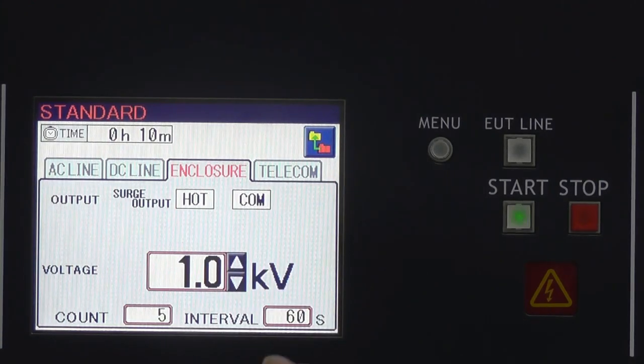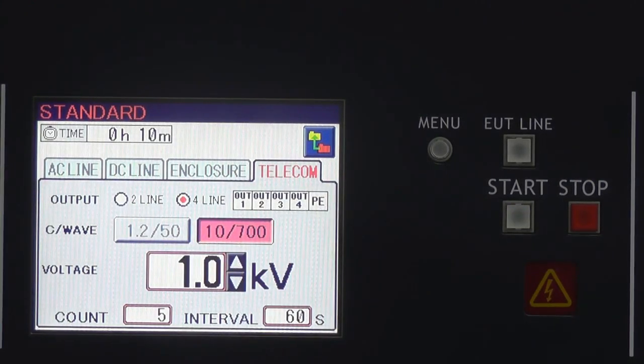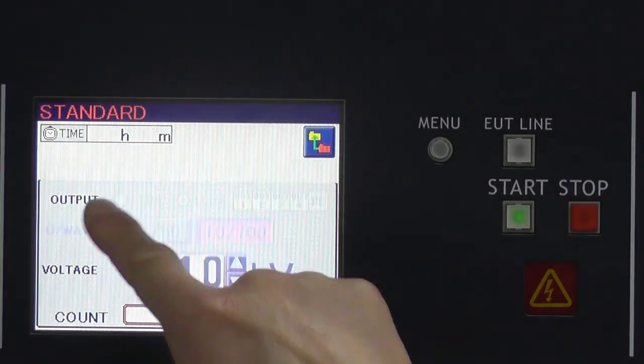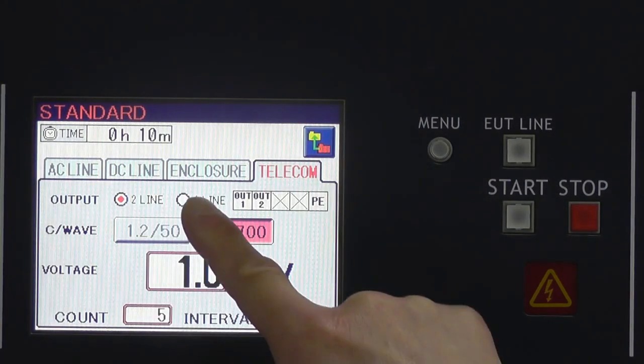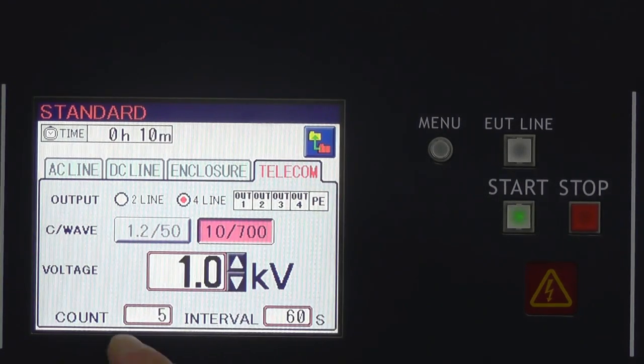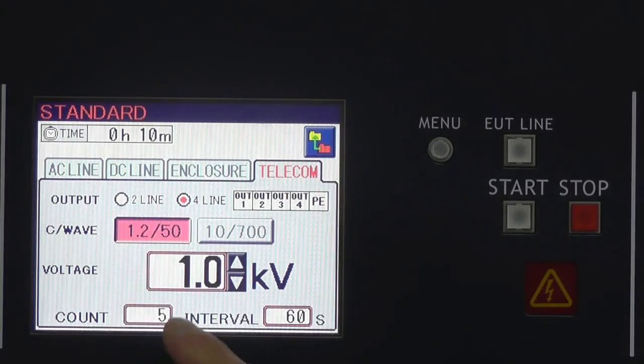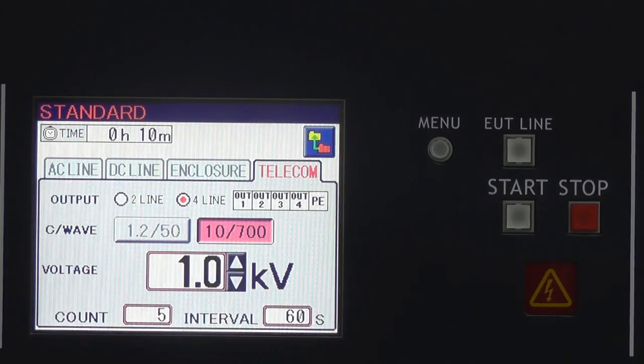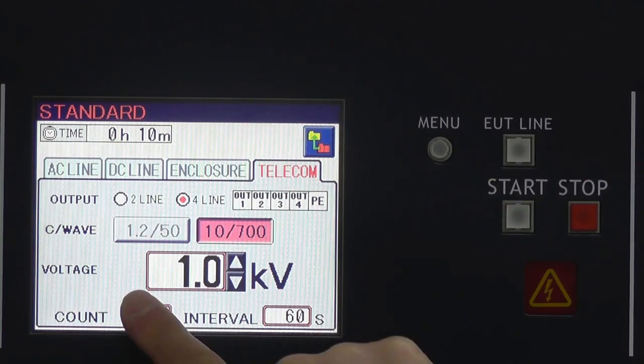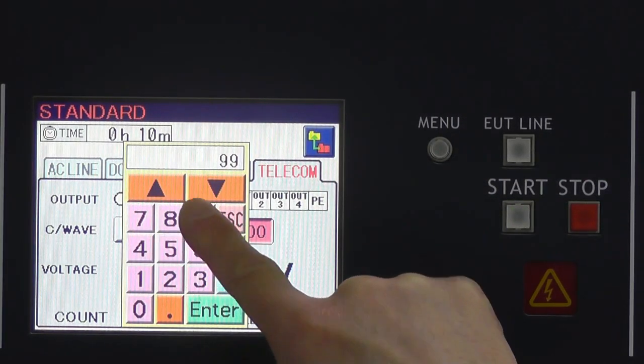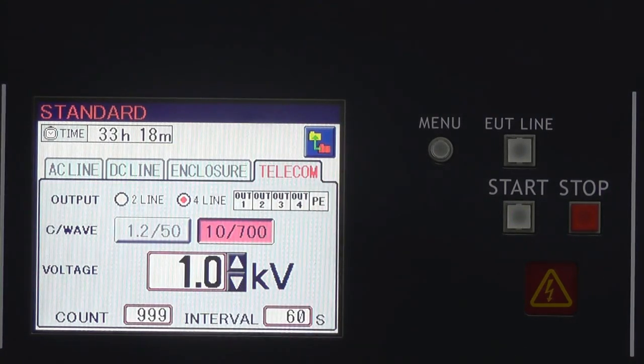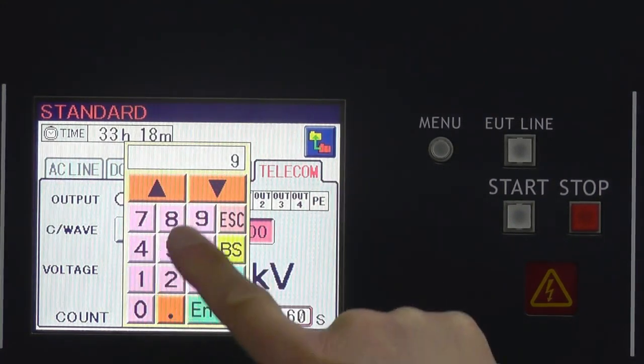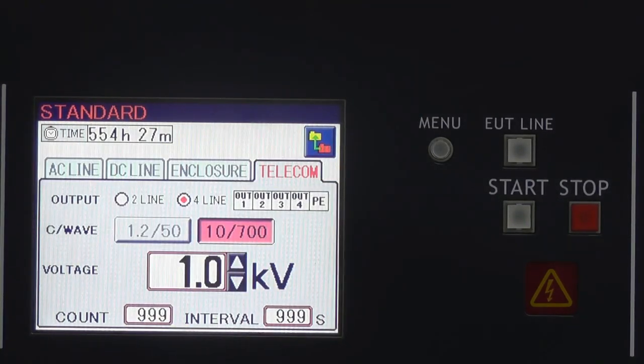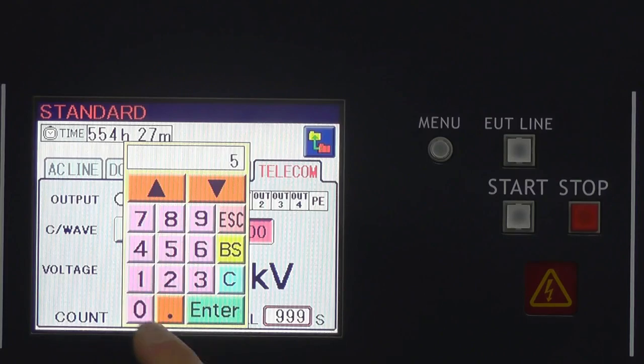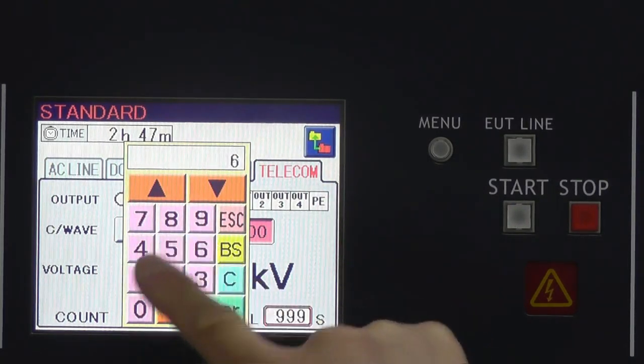use the enclosure menu here, and if it's a telecom test, simply press here, and that shows you might want to choose whether it's a 2-line system or a 4-line system here. And you also might need to choose the 1.2/50 or the 10/700 combination waves. And the counts here, this test system supports up to 999 counts, and the interval you can support up to 999 seconds. Well, today we make it easy with 5 counts and 60 seconds.